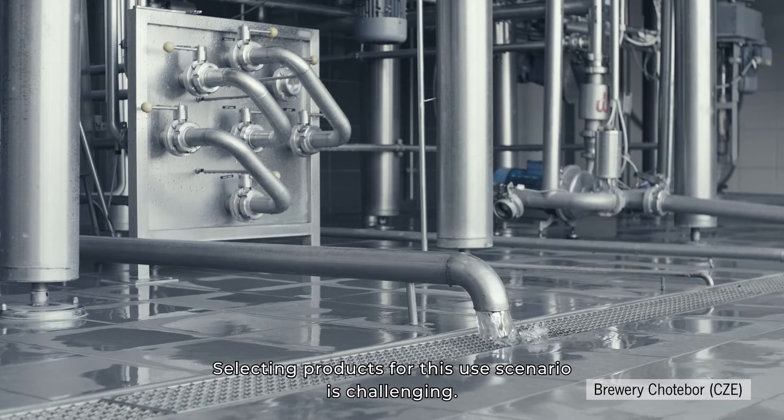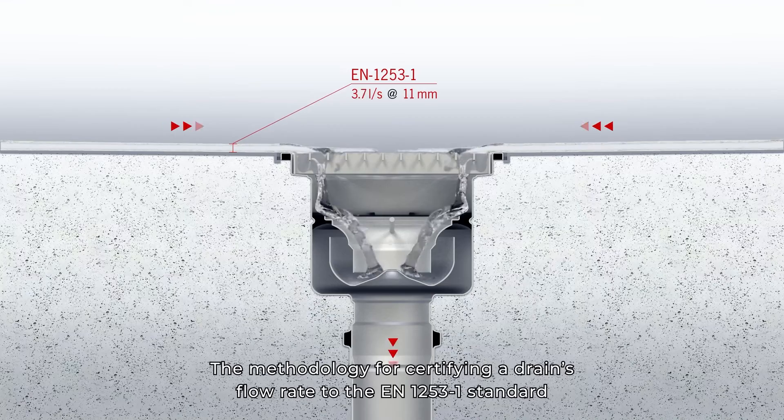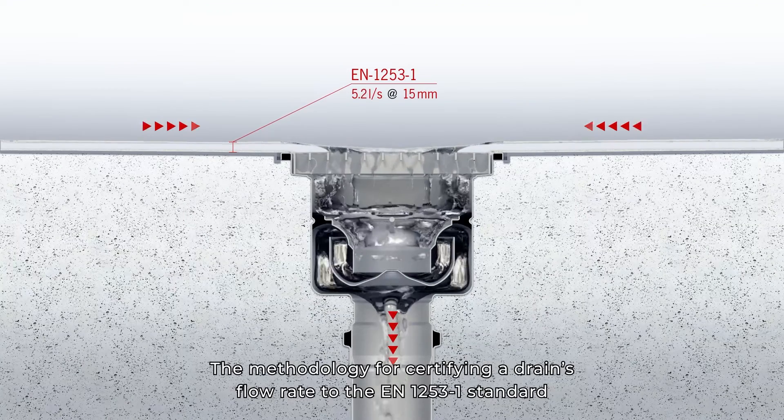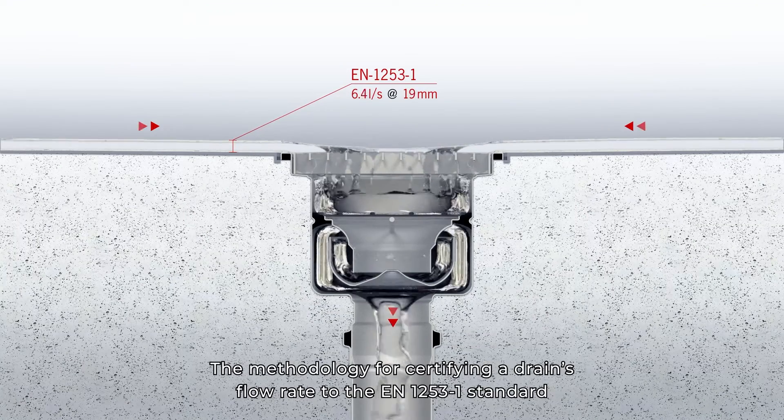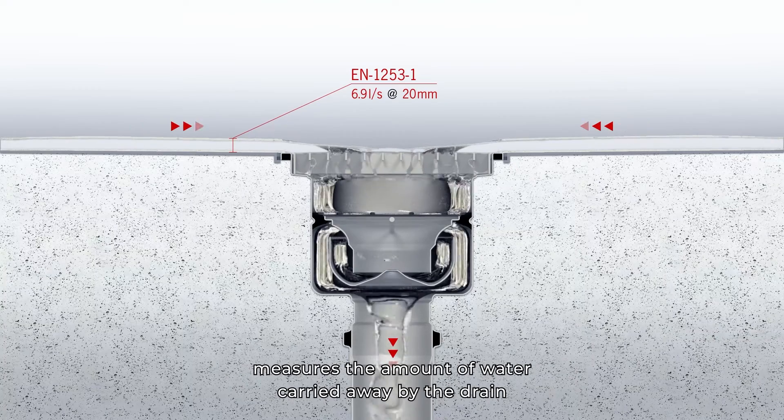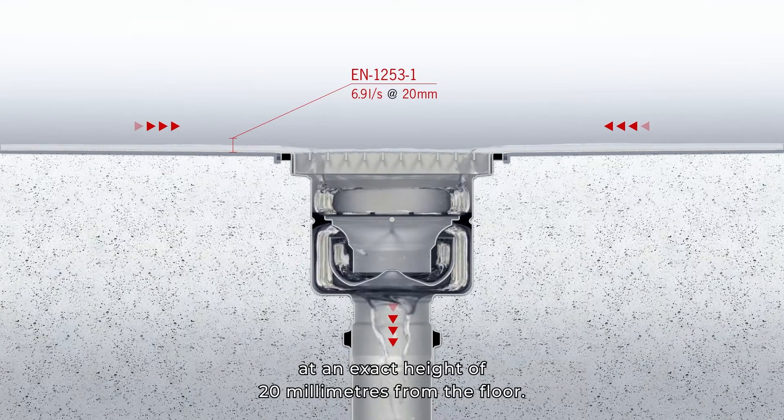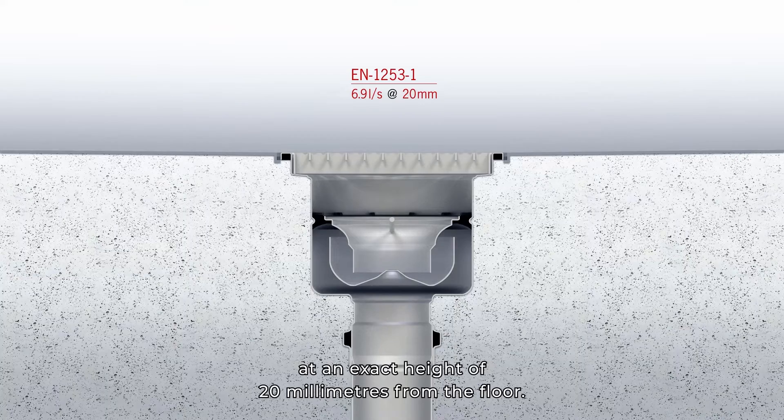Selecting products for this use scenario is challenging. Here's why. The methodology for certifying a drain's flow rate to the EN 1253-1 standard measures the amount of water carried away by the drain at an exact height of 20 millimeters from the floor.